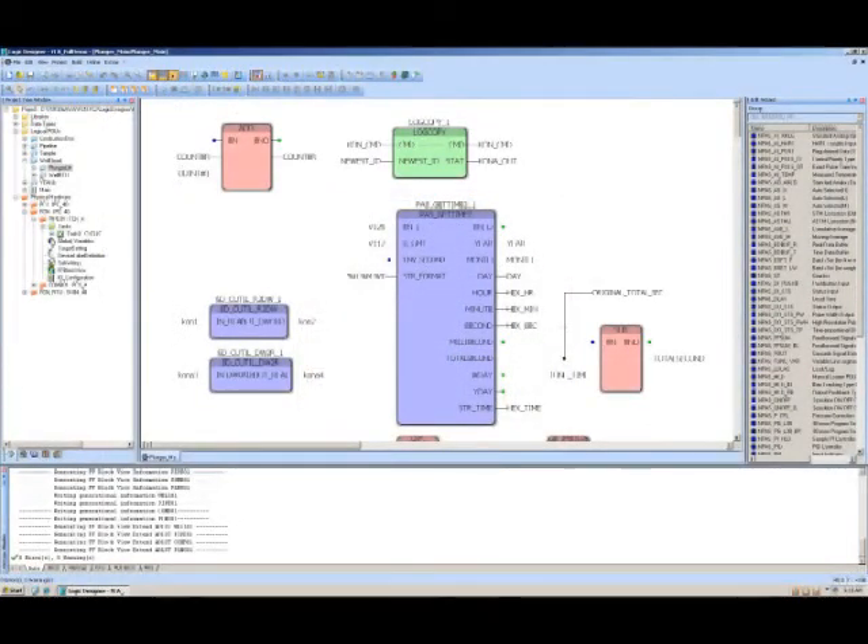Logic Designer is the software used for application programming. You can use all IEC 61131-defined languages, which are ladder logic, function block, sequential function chart, instruction list, or structured text, to program your applications. Smart objects such as user libraries and network templates can help you reuse components and speed up the programming process. Yokogawa also provides large libraries and portfolios including PROFIBUS, Modbus, DNP3, SAMA, Gas Flow Calculation, etc., to help you expand your application capabilities.